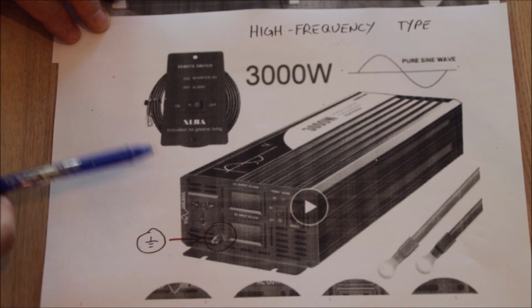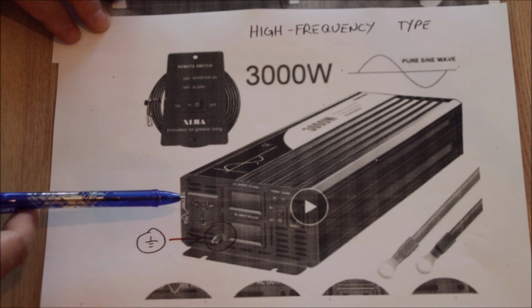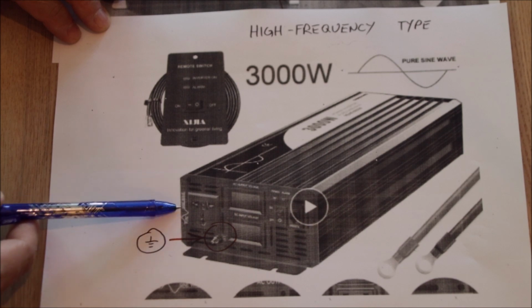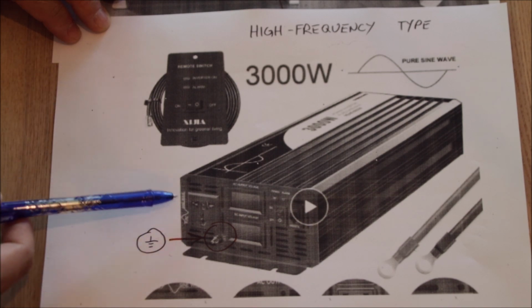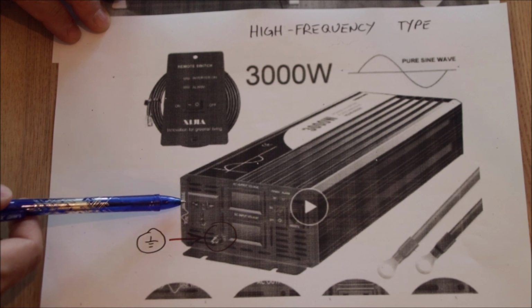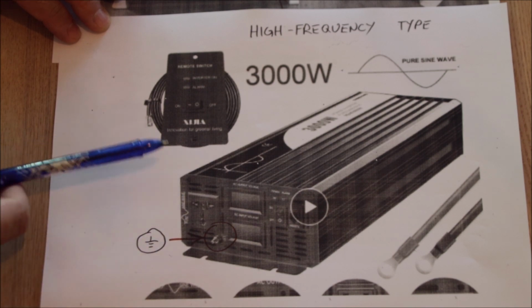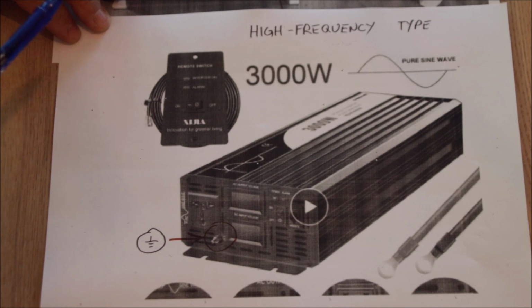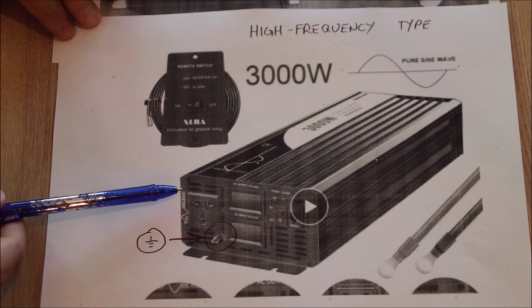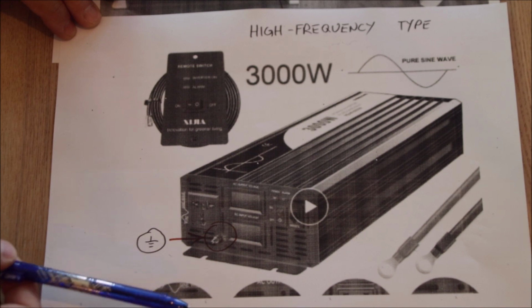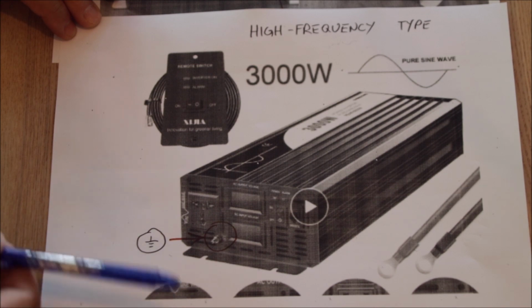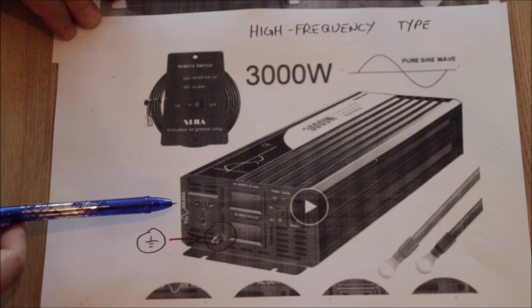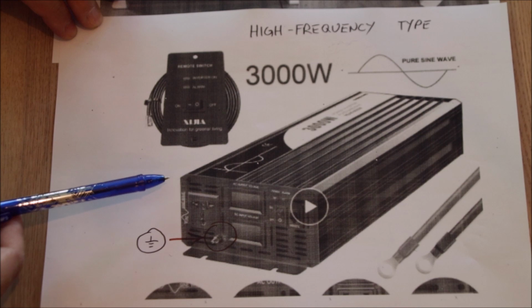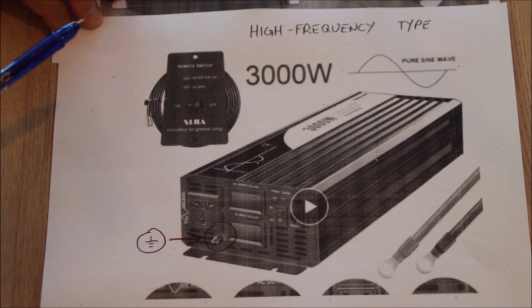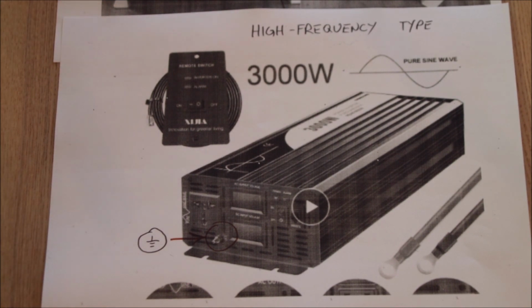They have the inverter, and then they have a socket, and you are supposed to use this socket straight with the device you want to run on it. So the worst thing you can do with this sort of inverter is connect an extension cable here, which again has like 3 to 5 sockets on it, and you fill up those sockets, because as I said, in the IT system, by having a fault on one of the devices, the fault can be replicated to the other devices. So this would not be the correct way. You can still use an inverter like this, and I will show you this, of course, in the installation schematic.